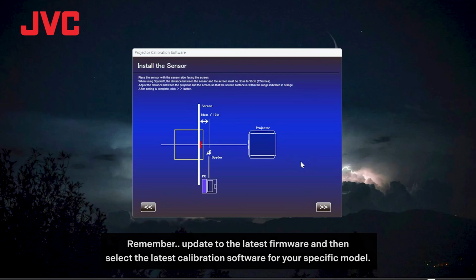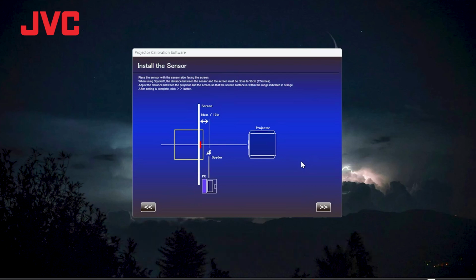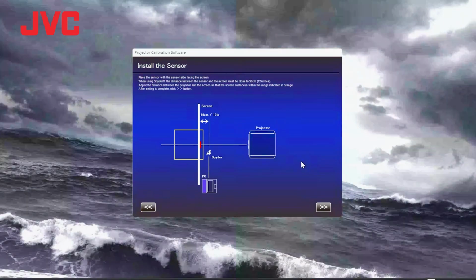As you bring up the calibration software and you've gone past the Spyder, you'll see a white field up on the screen. On your laptop, you'll see a GUI interface with a screen, which is a white vertical line, and then an orange box. That orange box really determines the sensitivity of the meter. So we want to center that orange box on the screen. It doesn't have to be exact. It just needs to be on the screen.